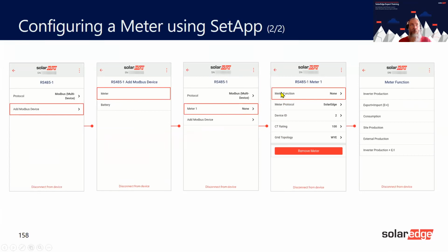Now, here's the important bit. You see on here, device ID 2. Because you're choosing meter 1, it's automatically going to put a 1 in here. So you need to change that to a 2. Do you remember we had the dip switches on the meter where we had meter 1 and 3 were off and meter 2, dip switch 2 was on? So meter 1 would automatically put 1 in here. You change that for a 2. The CT rating automatically appears. Then you've just got to choose your function.